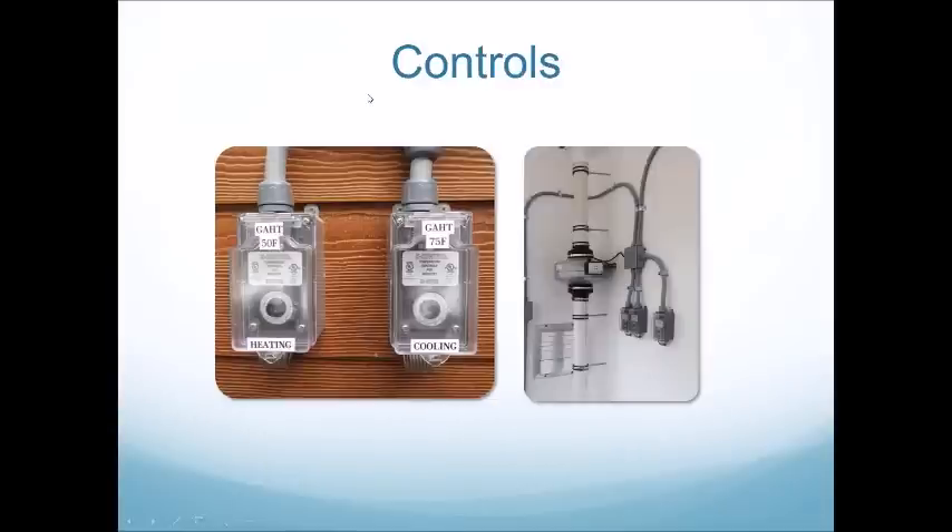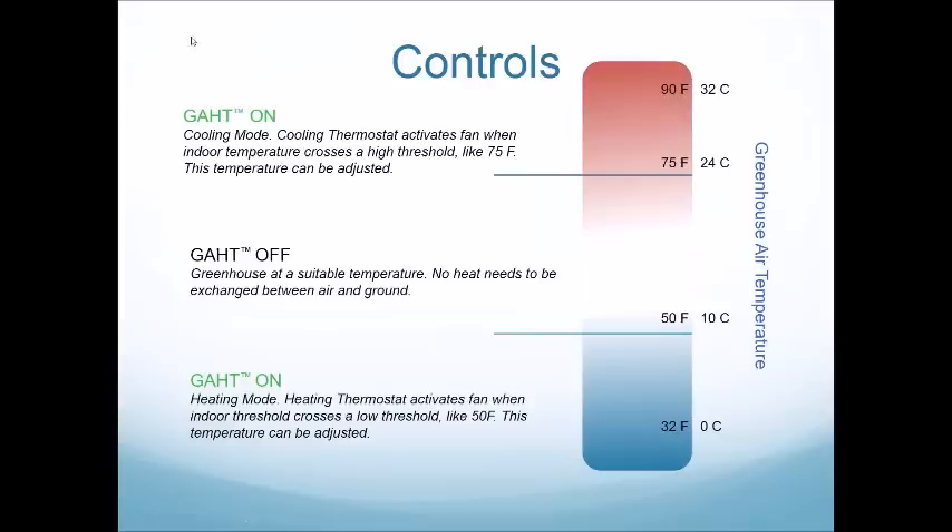Our GAHT systems typically require two thermostats: one for heating commonly set at 50 degrees Fahrenheit, and one for cooling commonly set at 75 degrees. The GAHT cooling thermostat activates a fan when indoor temperatures cross a high threshold such as 75 degrees Fahrenheit — this temperature can be adjusted. The GAHT will turn off when the greenhouse temperature falls between 75 and 50 degrees, then turn back on to heat when the thermostat falls below the set threshold of 50 degrees, which can also be adjusted.